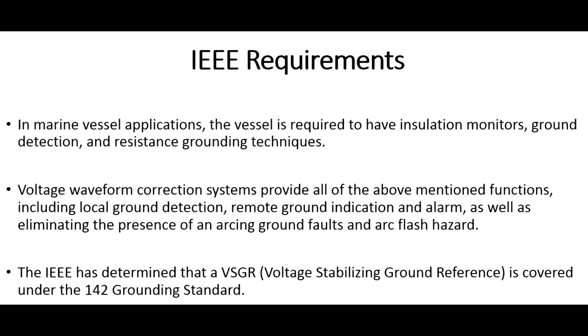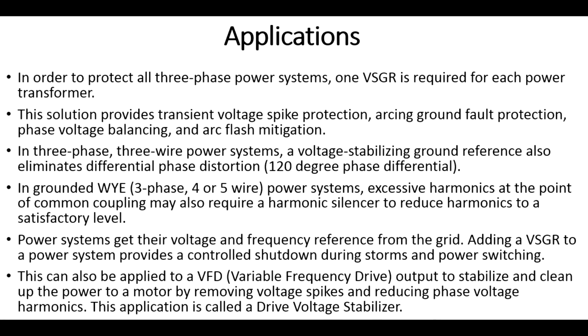As the IEEE discovered after 40 years of dictating the same standards, getting the same results, they were quite interested in our technology. We worked with them, and they have dictated that a voltage stabilizing ground reference is covered under their 142 grounding standard. How does this all work? Well, in application, you do not need to put this in at every drive or at each source of noise as you would with a TVSS. You simply have to install one per power transformer.